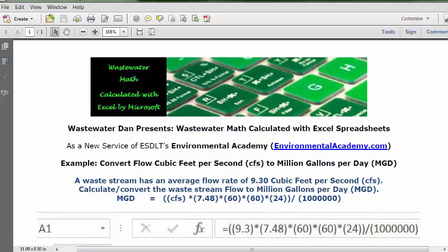and putting in all the basic elements for the calculation. We'll start out with CFS (cubic feet per second), multiply it by 7.48 to get gallons per second. Multiply by 60 to get gallons per minute, multiply by 60 again to get gallons per hour, multiply by 24 to get gallons per day, and divide by a million to give us million gallons per day (MGD).